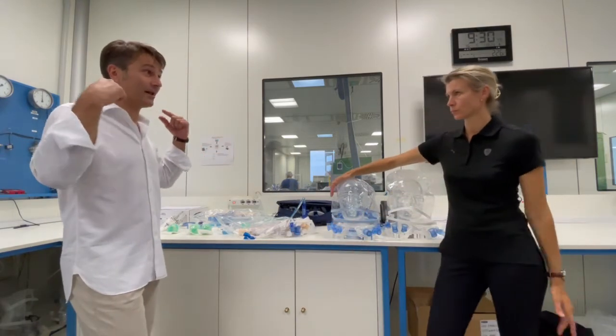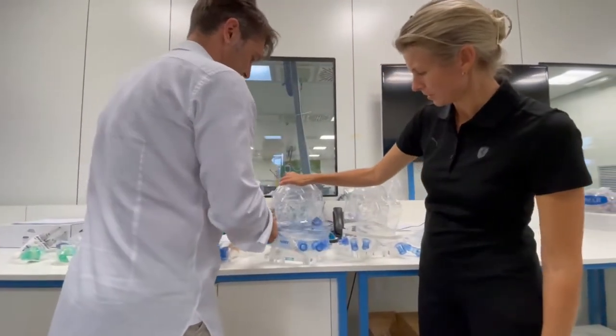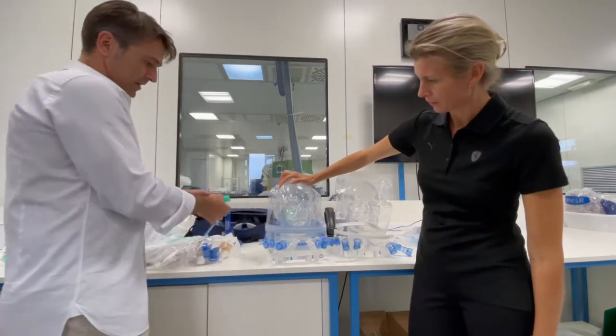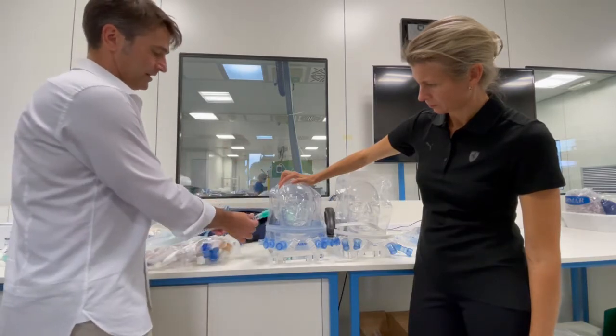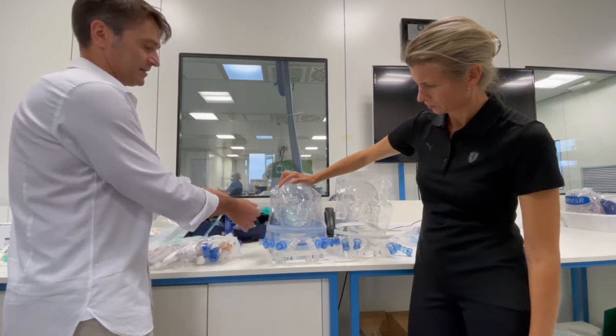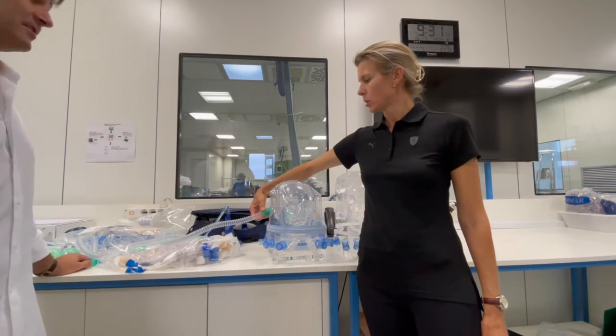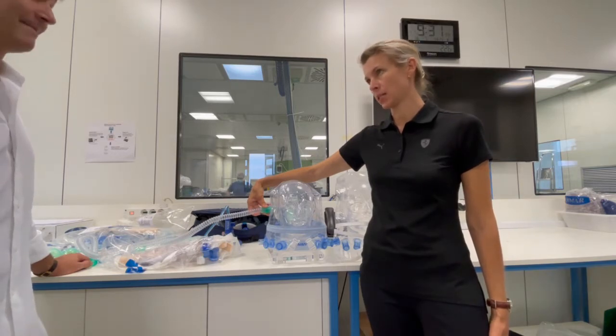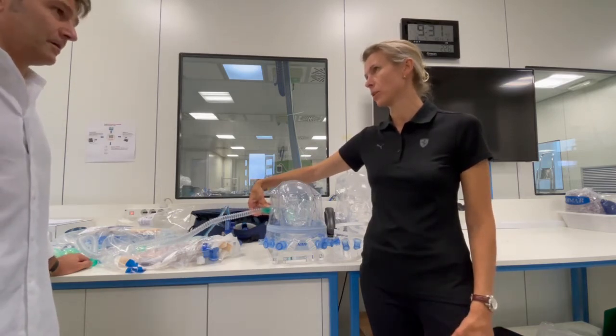It is important to keep the connectors stable and fixated. If you have connectors in front of the patient's airway, when you go up with pressure inside, the connector will move. This can confuse the ventilator — it will be recognized as a trigger, and the machine will not correctly read whether the patient is taking a breath or finishing one. It can mislead the ventilator, and this is why desynchronization happens.